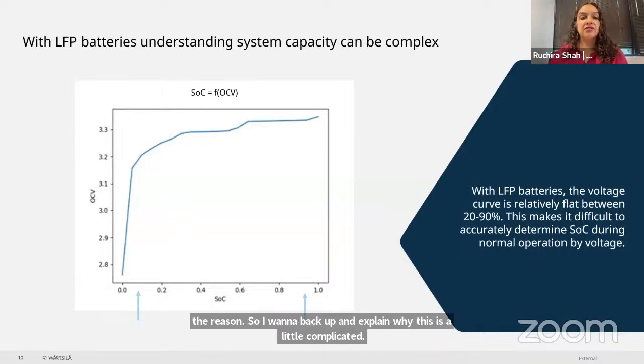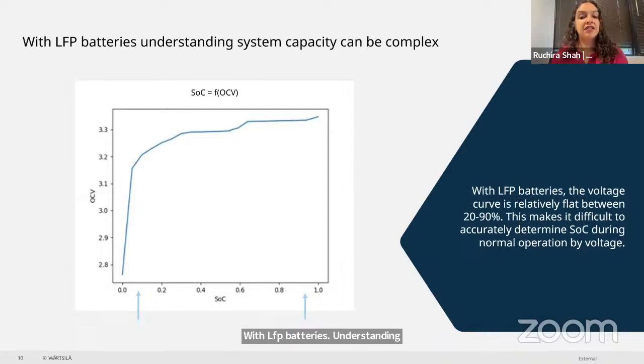With LFP batteries, understanding the true system capacity can be complex. The voltage curve is relatively flat between 20 to 90%, which makes it very difficult to accurately determine the state of charge during normal operation, since state of charge is estimated based on voltage. If your voltage curve is flat, it's challenging to understand the true state of charge of the battery. And if you continue to operate the battery between 20 to 90% and rarely go outside those bounds, that state of charge estimation can start becoming increasingly inaccurate.